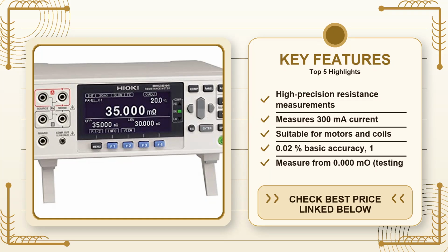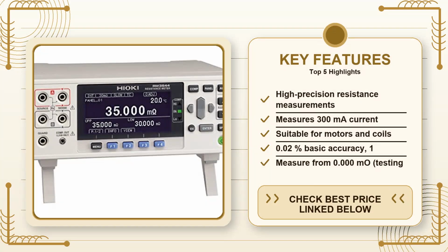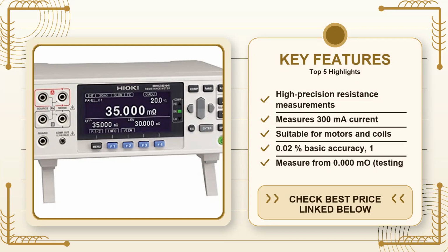If you spend a lot of time in noisy shops or near loud machinery, the optional LED comparator attachment and the high-volume judgment tones become more than a nice-to-have. The LEDs light up when the measured value hits a preset threshold, so you don't have to stare at the display while a hydraulic press is thumping nearby. The auditory tones work the same way, different pitch for different zones, so you can walk away a few feet, listen, and know if the resistance is still within spec. For someone checking a batch of solenoid coils on a production line, those cues shave minutes off each test, which adds up to hours saved over a shift.